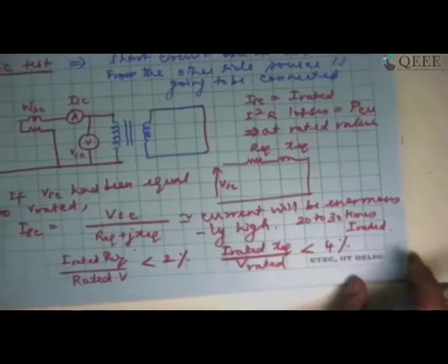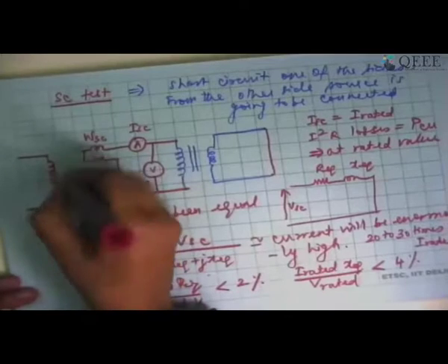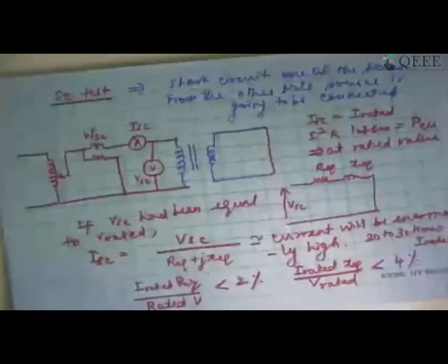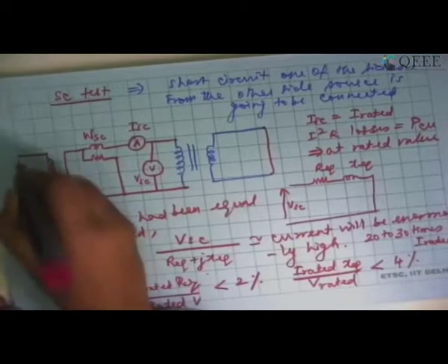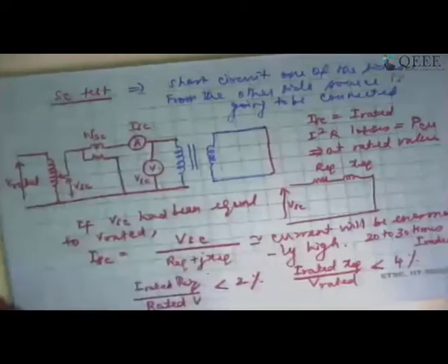That's the reason why normally what we do in the short circuit test is to apply the voltage using a variac. So I'm going to use something called an auto transformer, which we will talk about very shortly. And then I'm going to apply the voltage. So auto transformer is exactly similar to a potential divider. Only thing is it is made up of inductance rather than resistance. So I am applying V rated here, whereas what I am applying here is VSC, which is a reduced voltage.